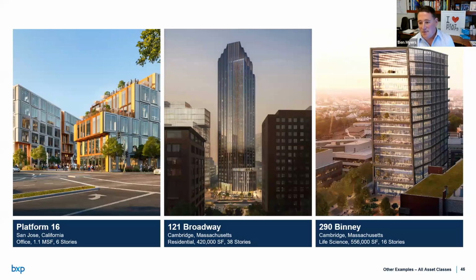Probably the most exciting project we're developing now is 290 Binney Street, a life science building in Cambridge, Massachusetts, 556,000 square feet, 16 stories. It has an air source heat pump system with heat recovery chillers and water source chillers. With advanced heat recovery, it will be primarily electric, with backup thermal coupling to the district system. Based on our modeling, we expect the building will run year-round using heat pumps only, which is very challenging for a life science asset given air change requirements. This is cutting edge for the company and for the industry, and I'm tremendously excited about 290 Binney.